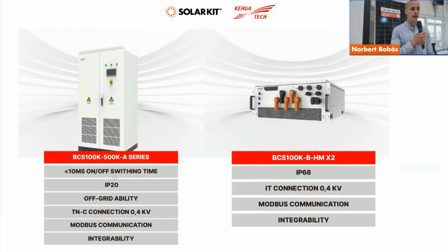The IT connection is recommended for PV parks, for example, where you don't have the neutral line, only the ground and the 3 phases. The TNC connection is recommended for applications where you have any kind of load connection, for example a factory.